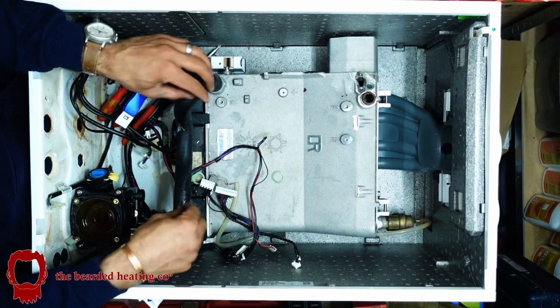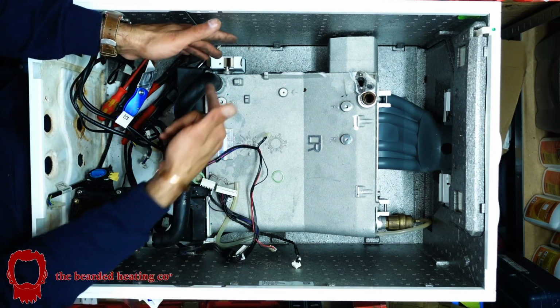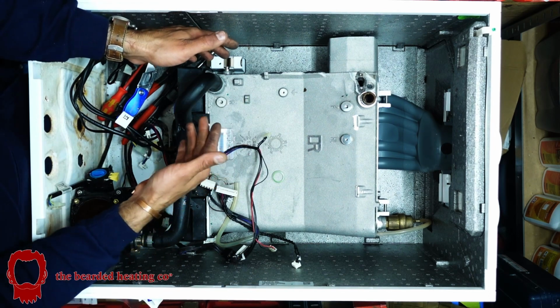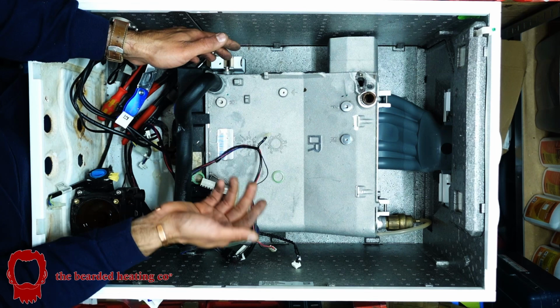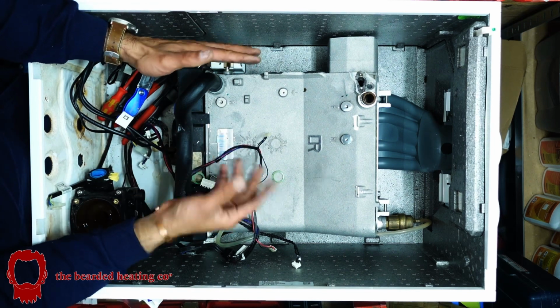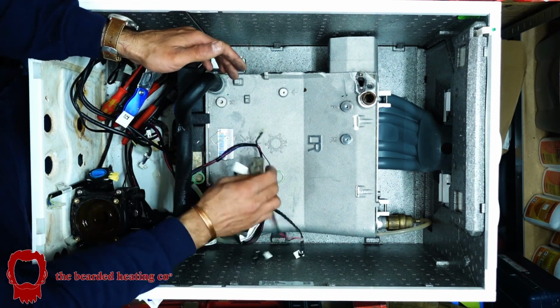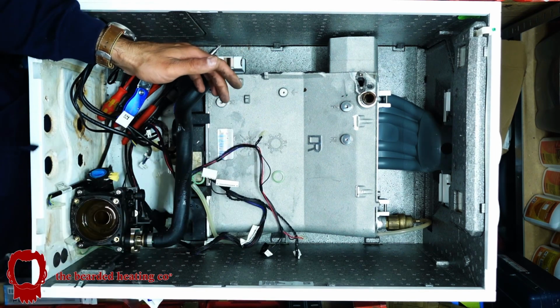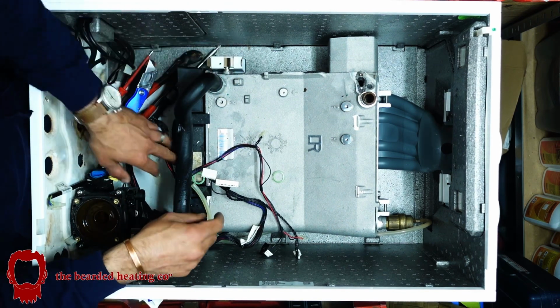If I was to ever change a heat exchanger on this boiler, I would always order new hose pipes. These flexible rubber hose pipes are not going back in or coming out in one piece - I have to cut them, so they won't be good to put back, and will need to be replaced as part of the heat exchanger job.